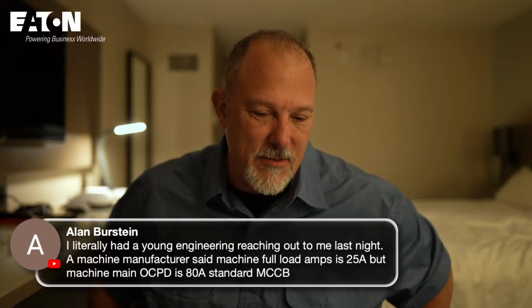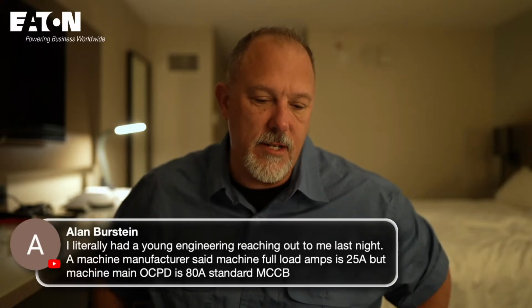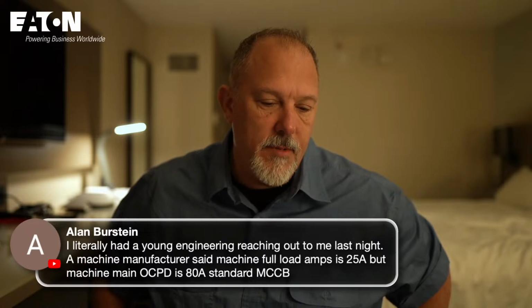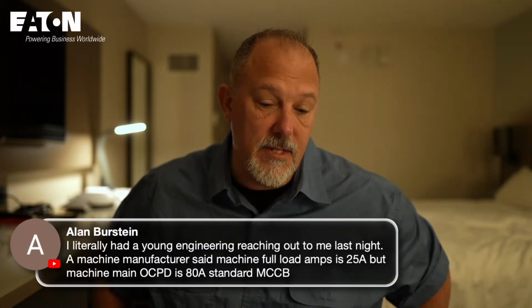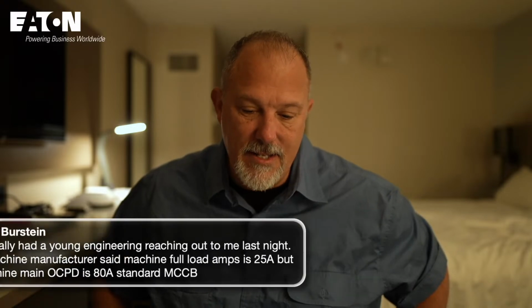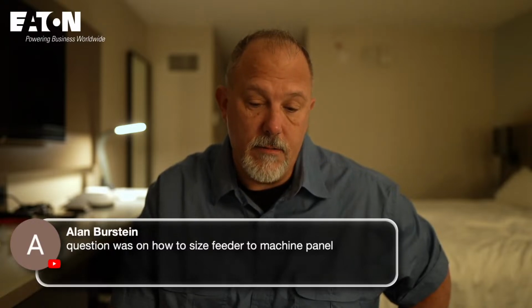I literally had a young engineer reaching out to me last night. A machine manufacturer said machine full load amps is 25 amps, but machine main OCPD is 80 amps, standard MCCB. Smarter power supplies. There we go. Alan, I missed yours. Question was on how to size feeder to a machine panel. Interesting. 25 amps, but the machine main overcurrent device is 80 amps. Now I wonder if that machine has motors that have inrush current issues.